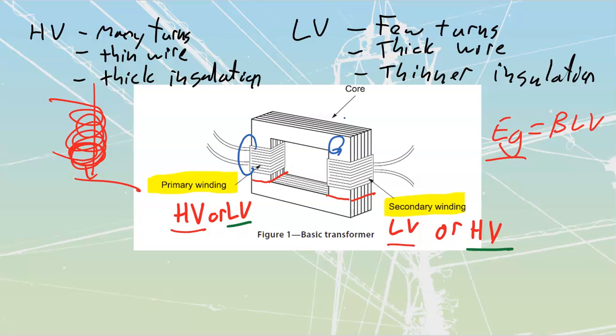Efficiency is always going to be my output compared to my input. We know that there's going to be losses on a transformer. If you've worked around one of these before, you have probably felt a small amount of heat coming off. They're wonderful places inside of electrical rooms. You see people drying their boots on top of them all the time because it's a nice gentle heat, but it is definitely consistent heat. Transformer efficiency is going to be that power out divided by my power in. What's the difference between power out and power in?